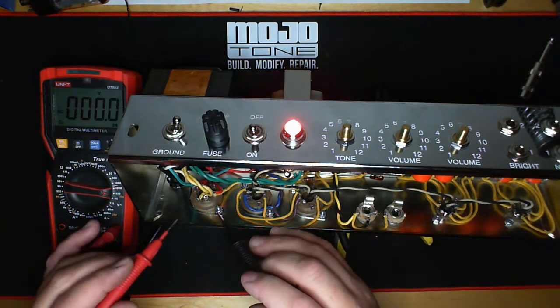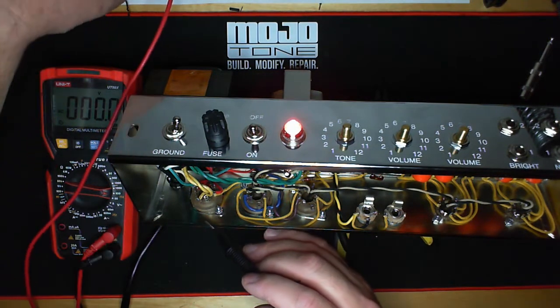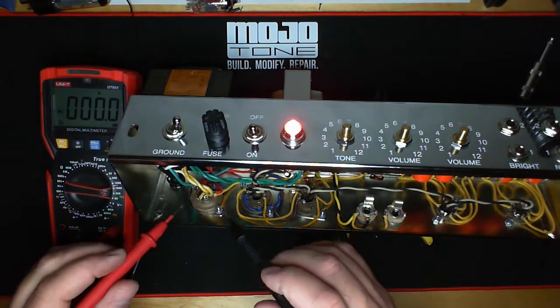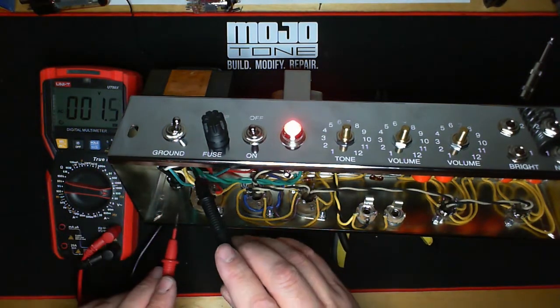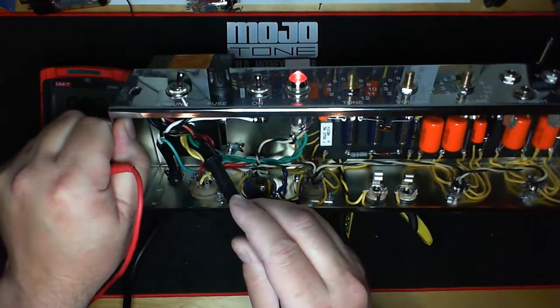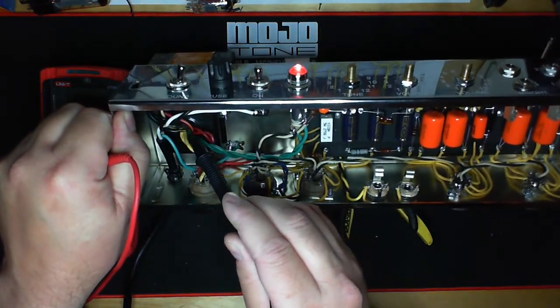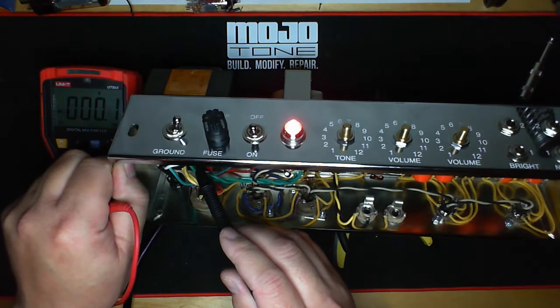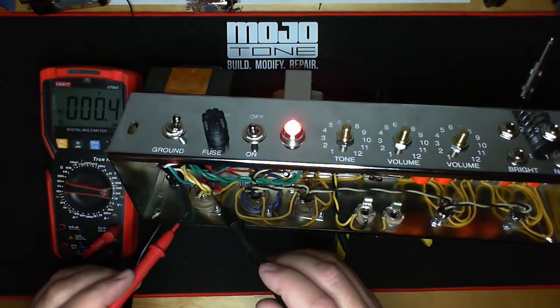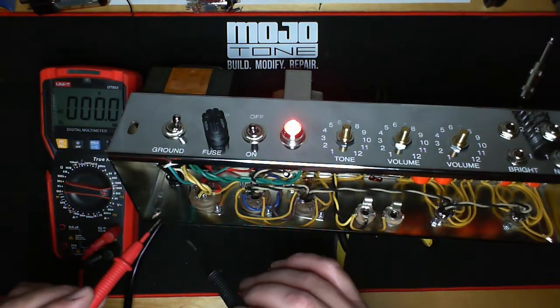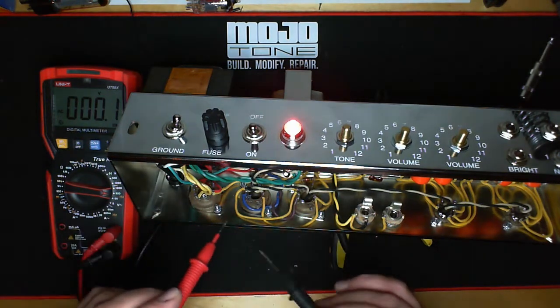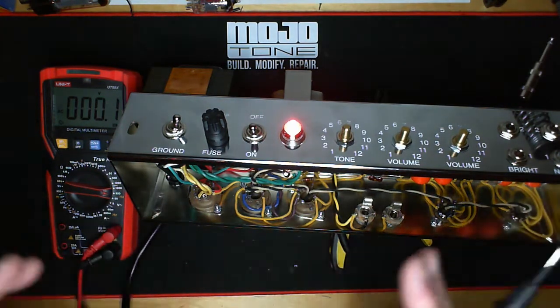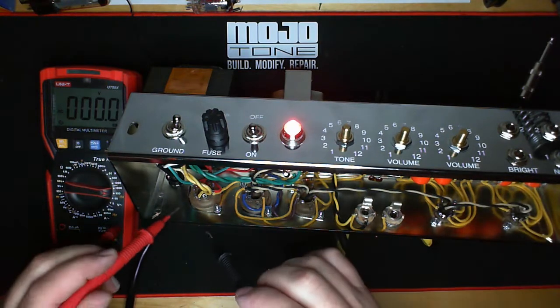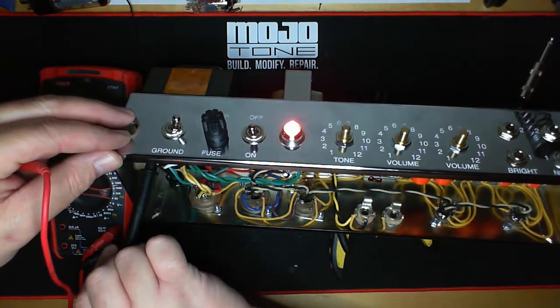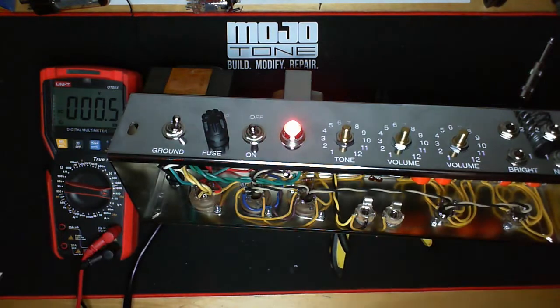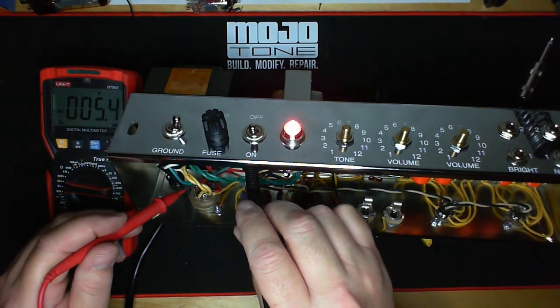So first thing I'm going to do is check pins 4 and 6, which are high voltage. Remember when we had the center tap here that goes to ground? That's our high voltage secondary. What we want to do is measure from wire to wire, but to check the transformer and make sure both sides of the high voltage coil are equal, I like to do both to ground. I'll go to ground to pin 4.